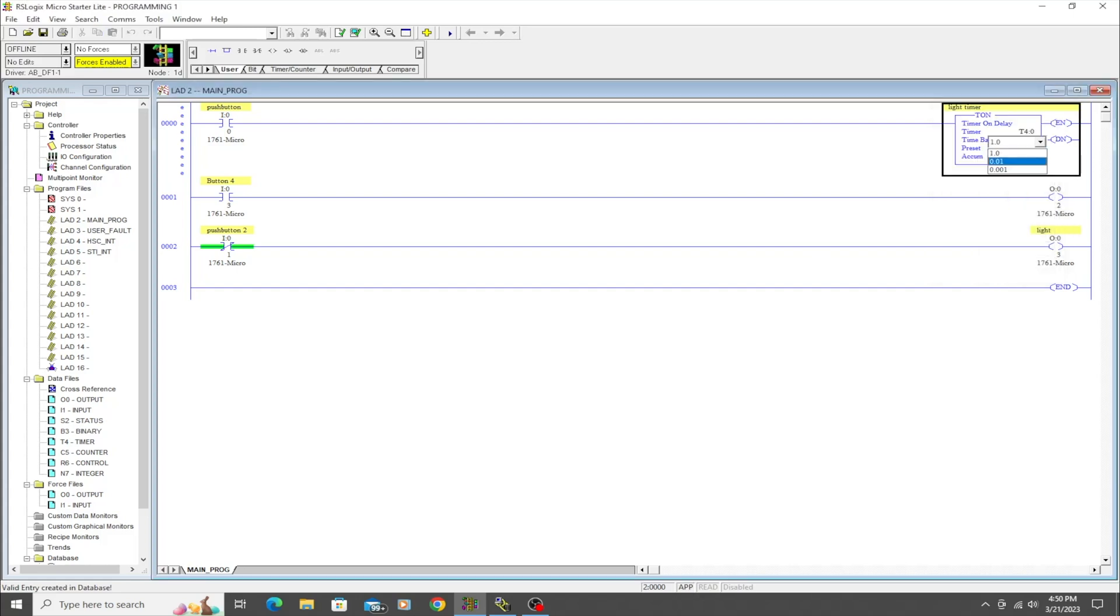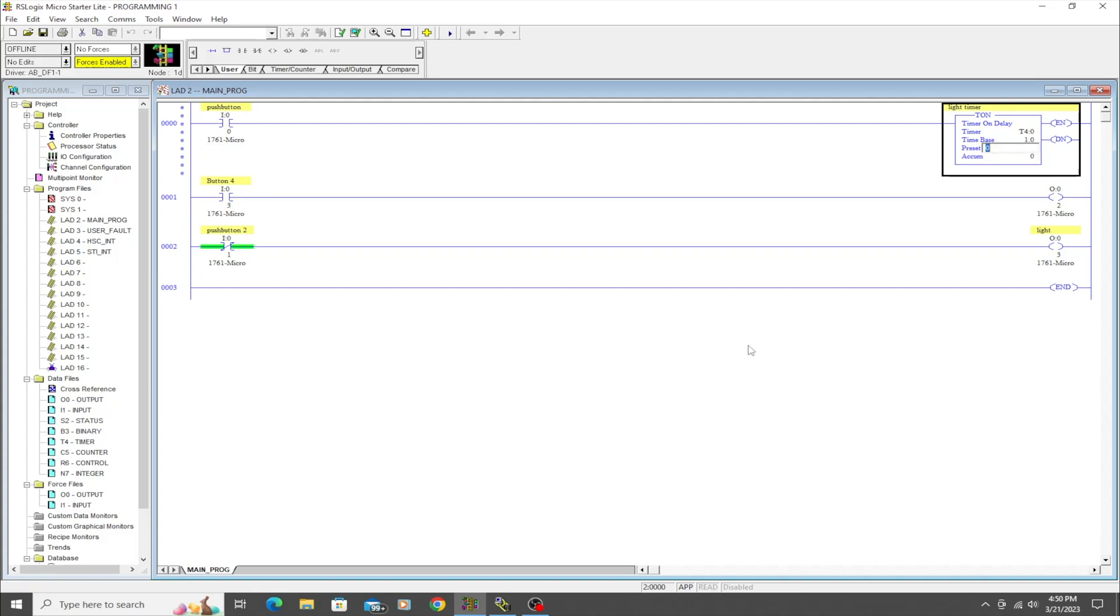So what we're going to do here is type in T4:0, and zero being that's the first timer that you can use. Since it's not being used in this program, I usually like to just start with the lowest numbered timer available, so we're just going to call this 'light timer'.